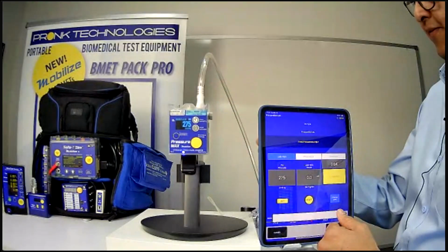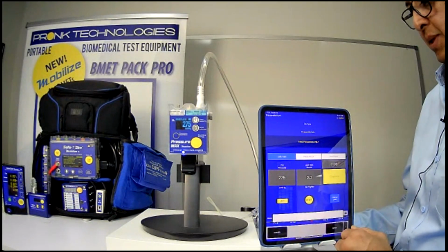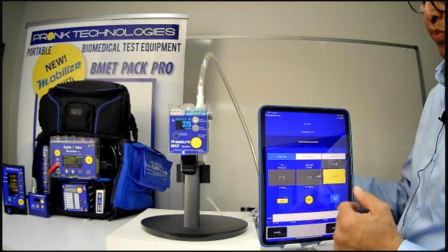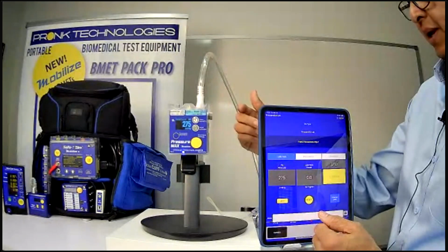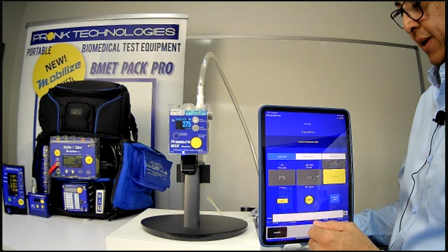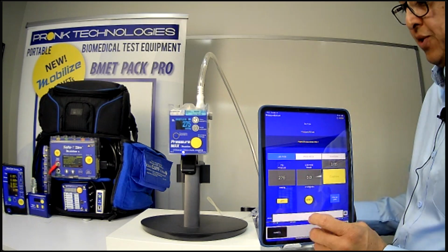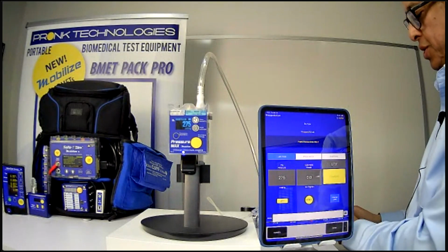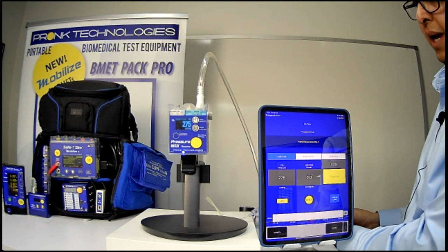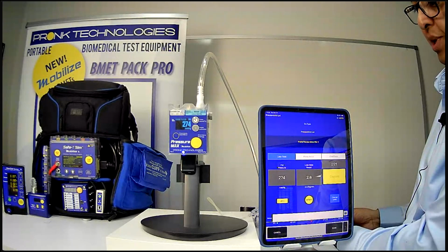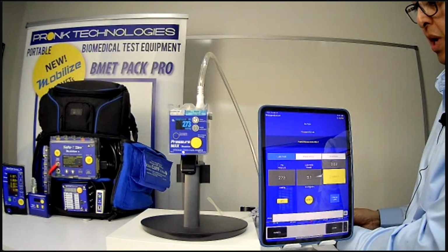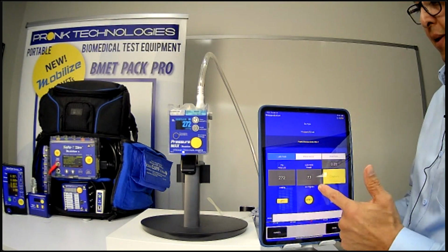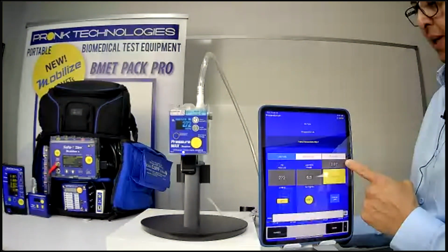So of course I don't have a medical device connected for the purposes of the demonstration, and because the Pressure Max virtually doesn't have any leak, you'll see that it really is not going to detect anything. So I'm going to intentionally lower the pressure a little bit, just so you can see the timer and how it works in detecting changes in pressure. As the pressure drops, it starts calculating the leak rate based on the elapsed time.